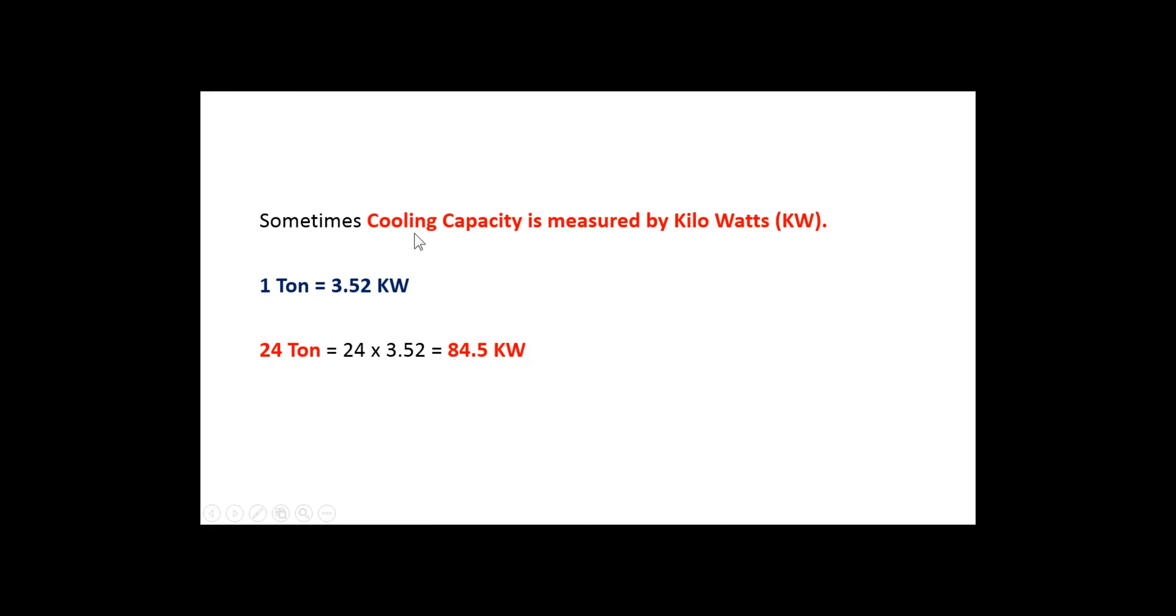Sometimes cooling capacity is measured by kilowatts. Here is the conversion from ton to kilowatts. One ton equals 3.52 kilowatts. Our requirement, as per our calculation, we found 24 ton chiller is required. Then, 24 times 3.52 equals 84.5 kilowatts.